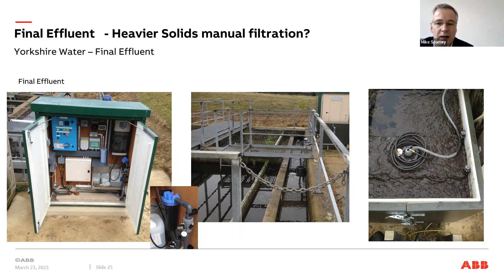The issue for that customer was their maintenance levels were a lot higher - it's about understanding the installation and where best to put the filtration or sampling pump. We've gained a lot of experience and honed our system since. This was another system within wastewater, final effluent, at a different water company site. Here we used a 100, and actually went up to a 200 micron filter on a rotor flush, which allowed for cleaning but also let it take in more sample, so it could last longer.